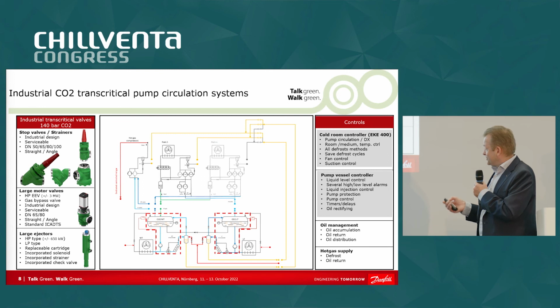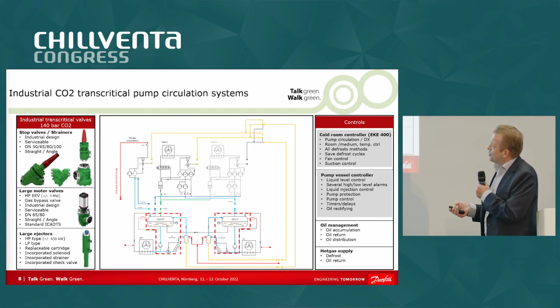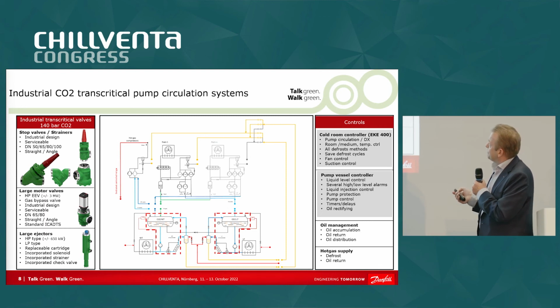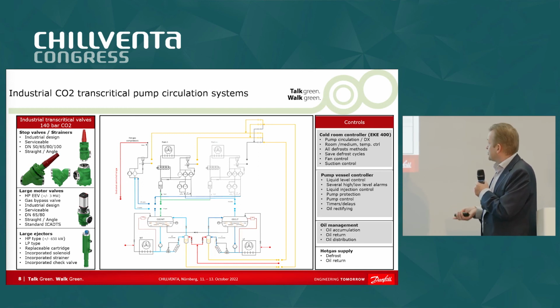And then oil management. So all the oil that collects at the end of the day here, we have to rectify. So a small part of it we send through an evaporator. You can accumulate the oil in receivers, and then you press them back to the racks. So you need to have a proper oil management. Also that we are working on.